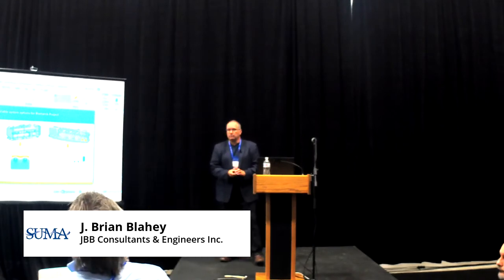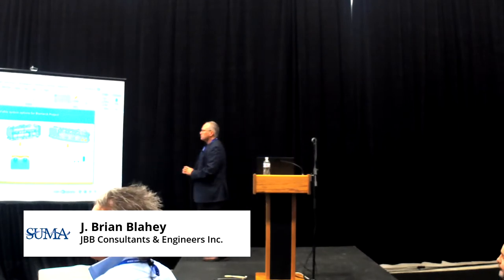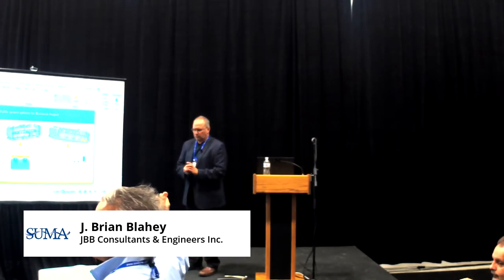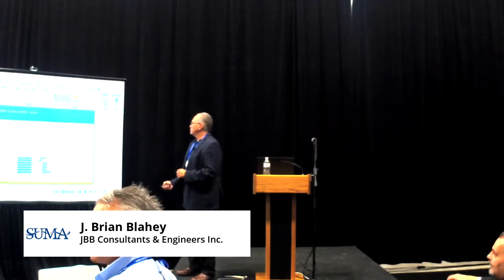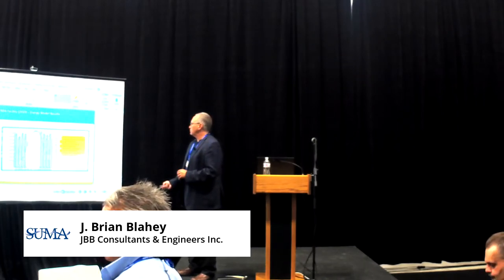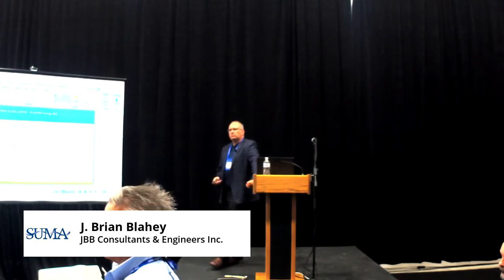Also, Brian, maybe you want to clarify a little bit about the compression and how, as the ambient temperature drops in a seasonal rink, your compressors actually don't run. I was affiliated with Brian in the United States installing that job in Bismarck. That's why in Canada it works so well: as the ambient temperature drops, you can cycle off your compressors and they don't run. So that package runs a lot longer before you have to overhaul your machines or replace your compressors. On a day like yesterday, they're probably all going to run because it got warm. But at 30 below, you're going to run your ice plant with no compression or very little. That's what the savings is.